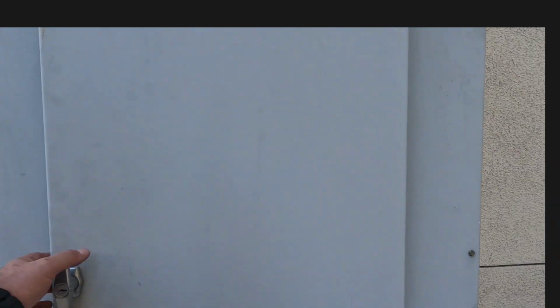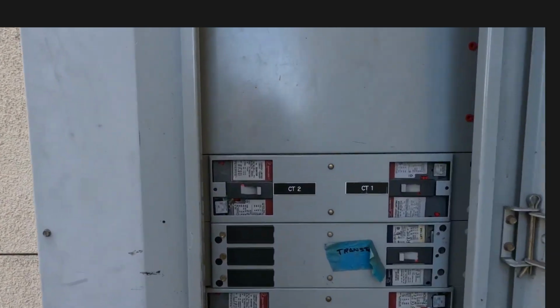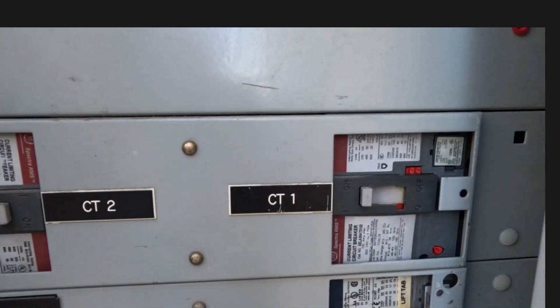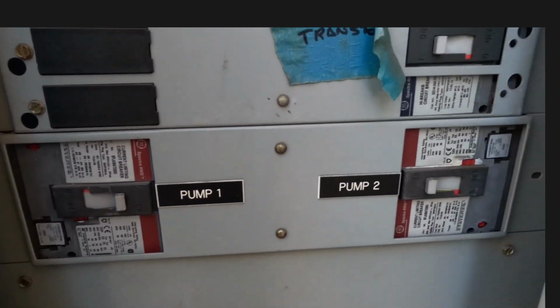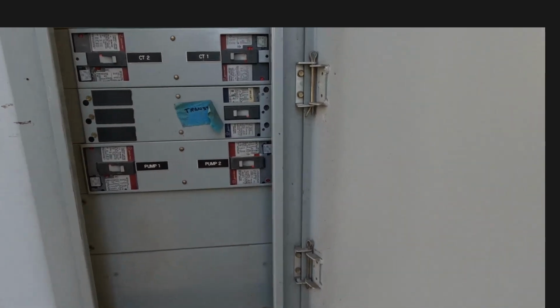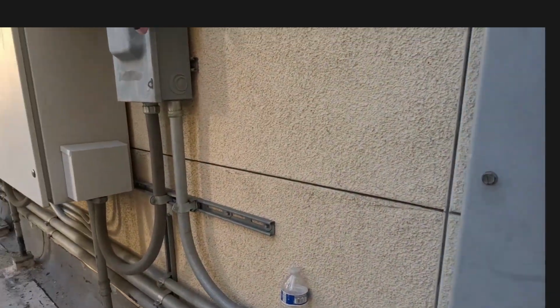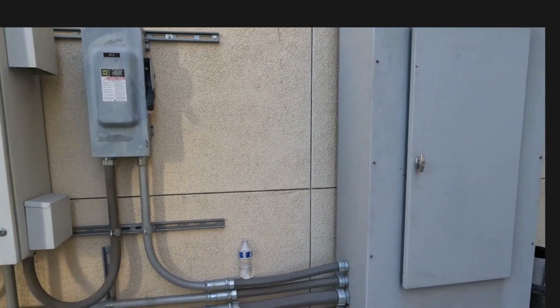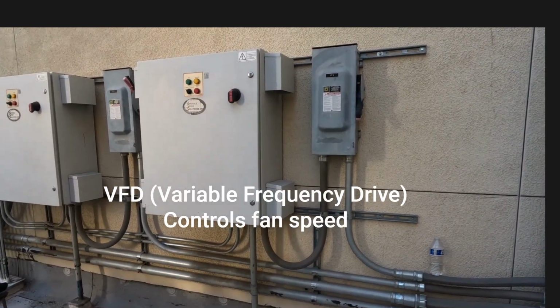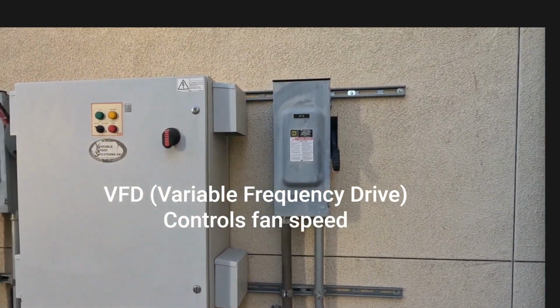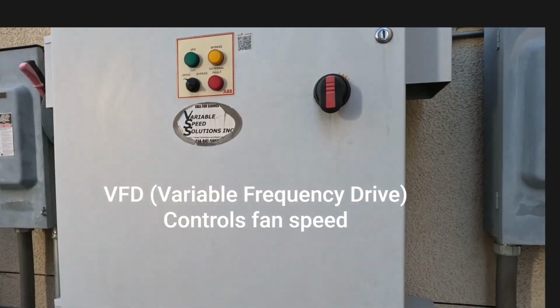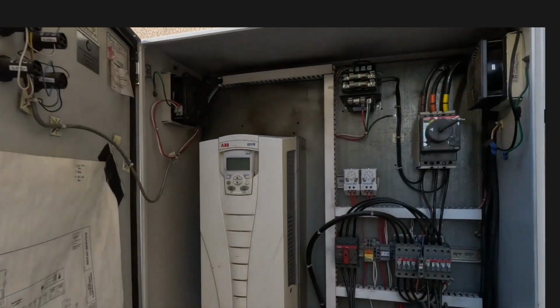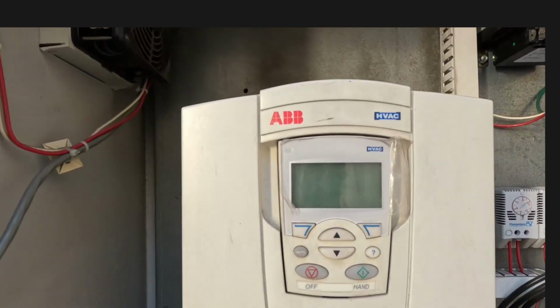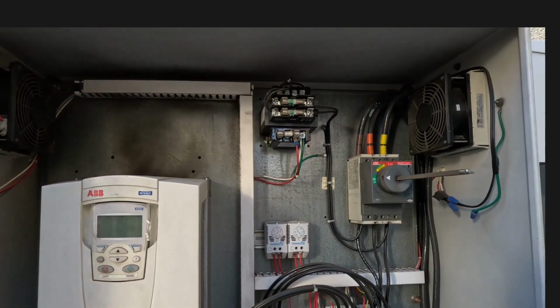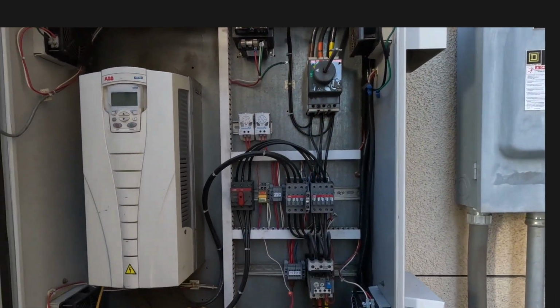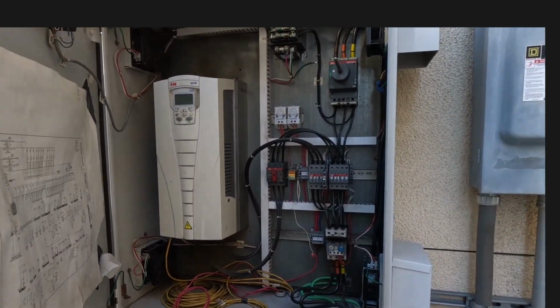Here's your breaker, right? You got breakers for cooling tower 1, cooling tower 2. Then we have breakers for our pump 1 and 2 right there. Breaker panel right here provides power to the cooling tower VFD. So then we have a disconnect here. And then downstream of that, we have the VFD, which controls the speed of those fan blades that I was checking. Currently, as you can see, I have everything up right now because I was in that cooling tower. I didn't want that thing running while I was performing my service and inspection.